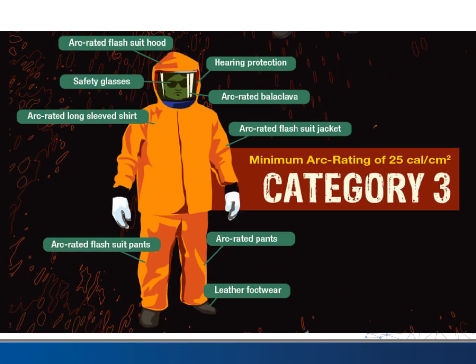Category three is where it starts to get a little more inconvenient. This is between eight and 25 calories per centimeter squared. You'll sometimes hear electricians refer to the 'beekeeper suit' — this is where they have to put it on. It's an arc-rated flash suit with pants and a jacket and a full shield. This is when it starts to kind of impact their ability to work.